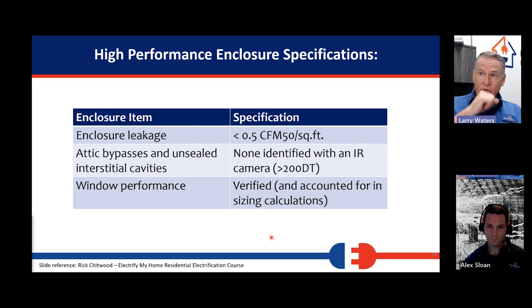All right, so really high performance enclosure specifications. If you were to consider a house a high performance enclosure, this is what you would need. You would need 0.5 CFM50 per square foot on a blower door test. Most houses are not this tight. As a matter of fact, a lot of the houses we test are 2 CFM50 per square foot. So if it's a 1,000 square foot house, oftentimes we have 2,000 or more CFM50 of leakage. If we can get a house to 1 CFM50 per square foot, which is kind of what we shoot for, we think that's a pretty good envelope. But high performance is 0.5, so half that much.